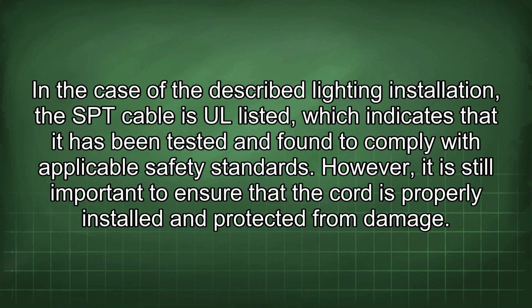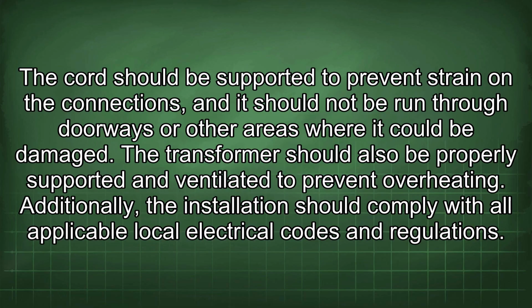In the case of the described lighting installation, the SPT cable is UL listed, which indicates that it has been tested and found to comply with applicable safety standards. However, it is still important to ensure that the cord is properly installed and protected from damage. The cord should be supported to prevent strain on the connections, and it should not be run through doorways or other areas where it could be damaged. The transformer should also be properly supported and ventilated to prevent overheating. Additionally, the installation should comply with all applicable local electrical codes and regulations.